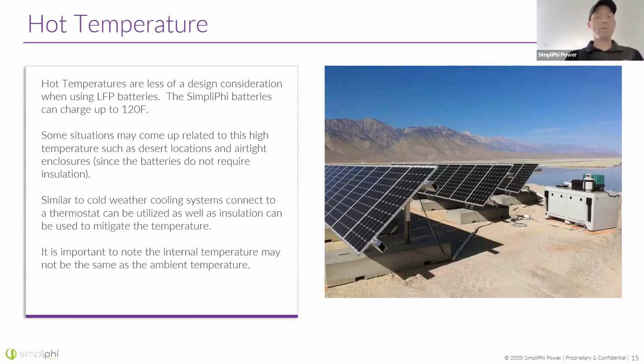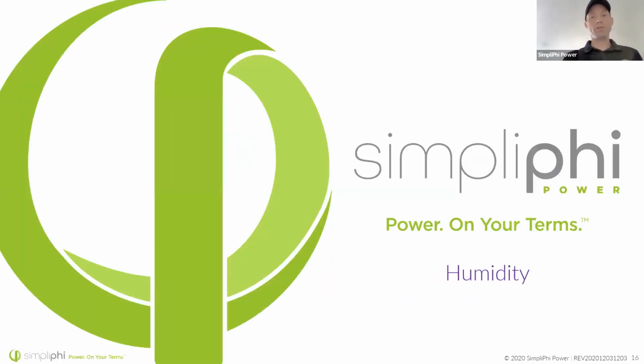And it's important to note that the internal battery temperature may be different from ambient temperature. So there are a couple of factors at play there. There's the thermal mass of the battery, meaning that the battery itself takes some amount of time to change temperature because it has some thermal inertia, so it will change more slowly than the environment, and then air especially. But the battery is also producing heat, as we mentioned.